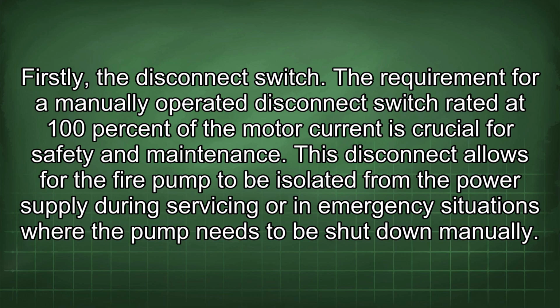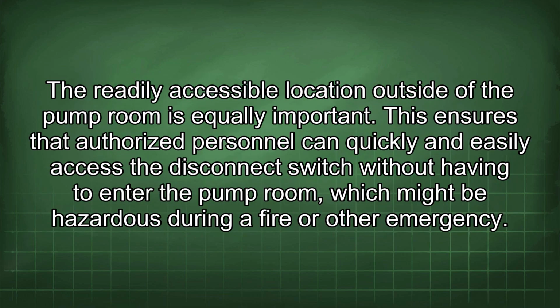Firstly, the disconnect switch. The requirement for a manually operated disconnect switch rated at 100% of the motor current is crucial for safety and maintenance. This disconnect allows for the fire pump to be isolated from the power supply during servicing or in emergency situations where the pump needs to be shut down manually. The readily accessible location outside of the pump room is equally important. This ensures that authorized personnel can quickly and easily access the disconnect switch without having to enter the pump room, which might be hazardous during a fire or other emergency.